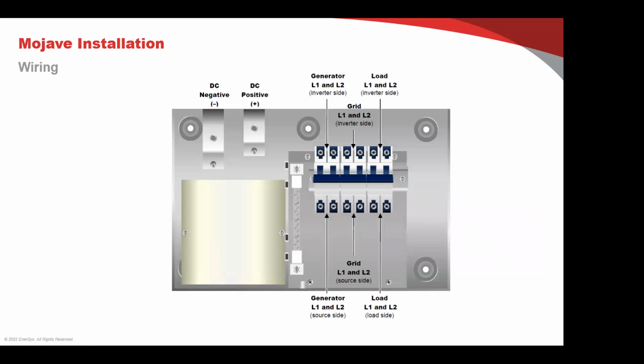And then in terms of wiring, again, your DC connections go here, the neutral connection, your grid AC input goes L1 and L2 here and here. These are pre-wired from the inverter up above. If you add a generator, you get this breaker from us. It's a 6-amp breaker. It's just DIN mount, just clips right in. You will have to put the wires up into the inverter though. You will have to take the inverter front cover off to do that. Add a generator, then put your L1, L2, neutral and ground connections.